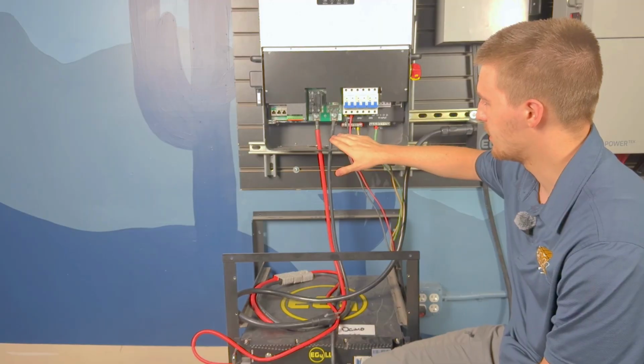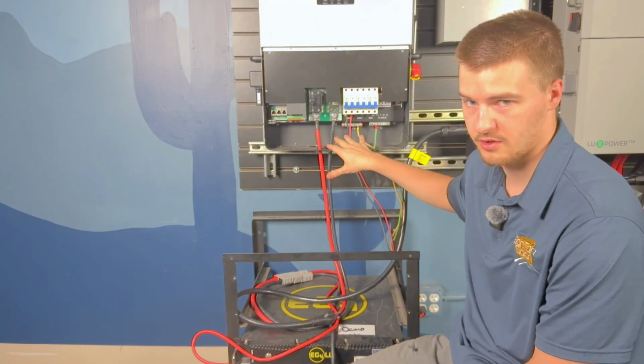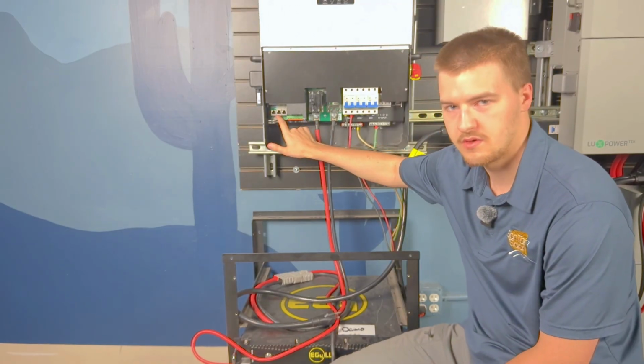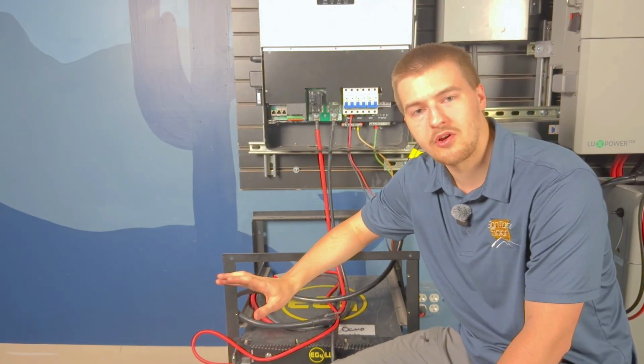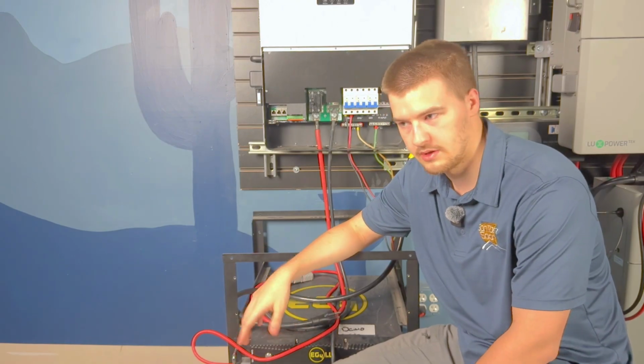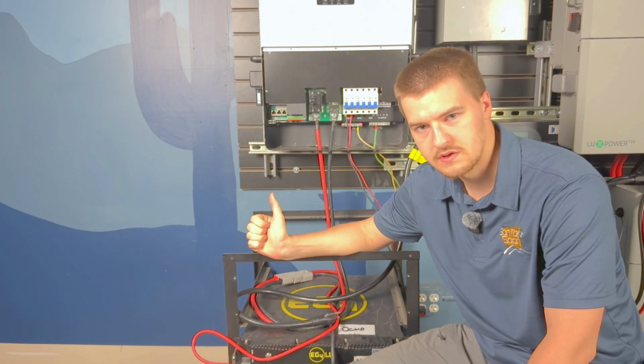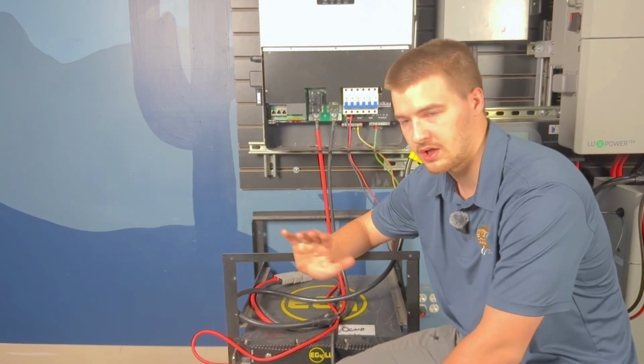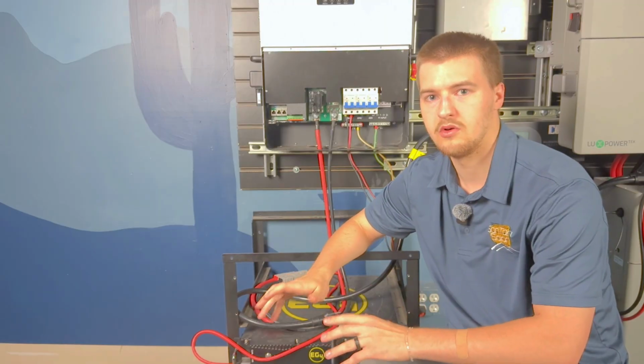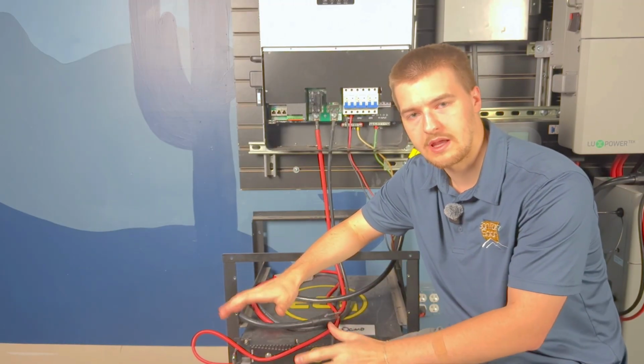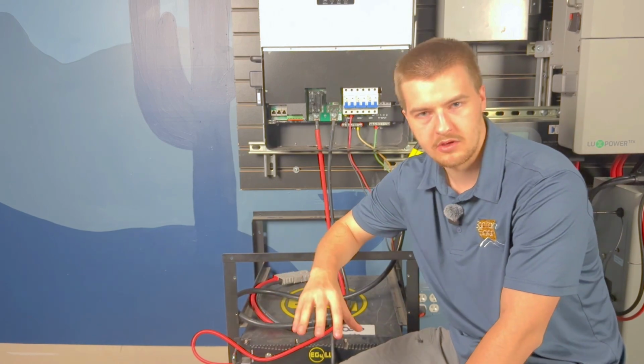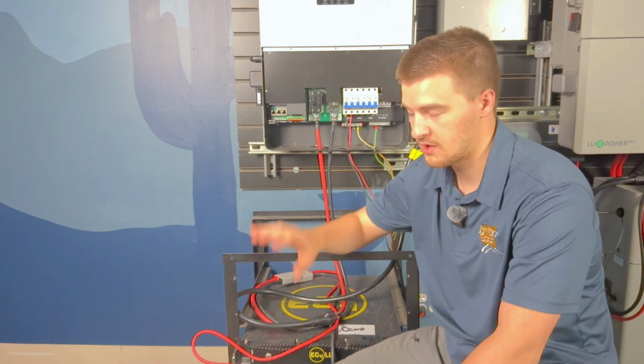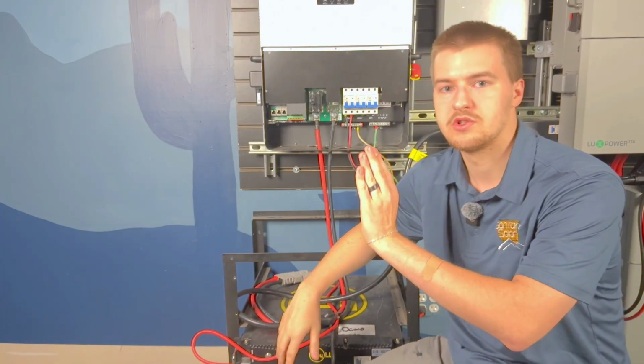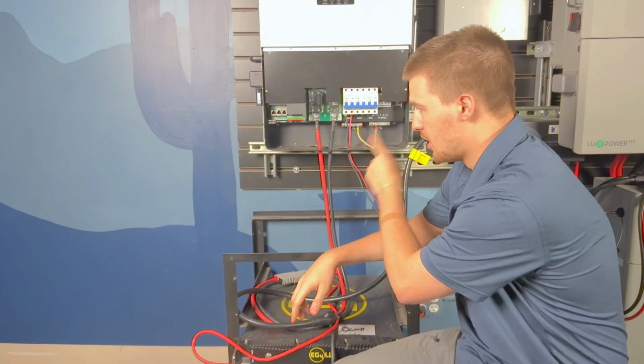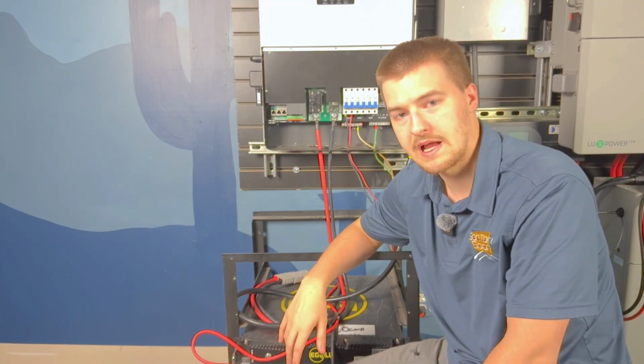I'm going to show how to connect to a loads panel with one inverter, and then how to parallel them with two inverters. The past couple weeks I've been getting a lot of calls on troubleshooting an inverter, but I always go over hardware first, and a lot of it has been wrong recently. So I want to make a video to clear all that up, so you can watch this, make sure your hardware is correctly installed and properly connected before you call me for troubleshooting. As long as the hardware is connected properly, software becomes a lot easier. But if hardware is not connected properly, software is an absolute nightmare. So let's get right into it.